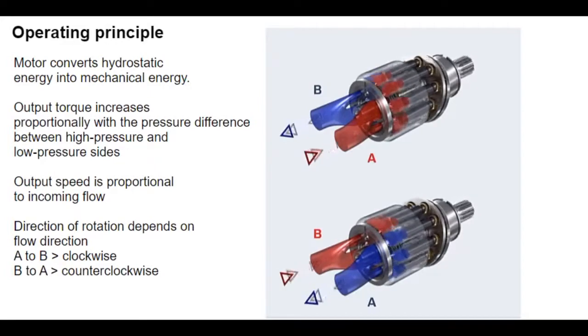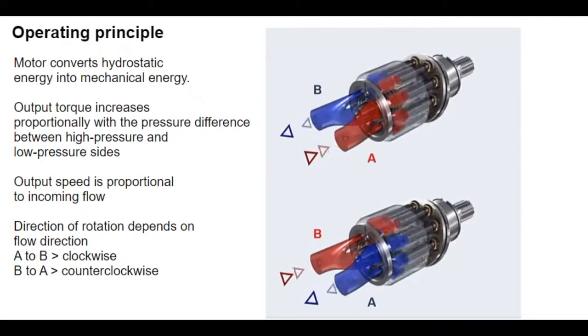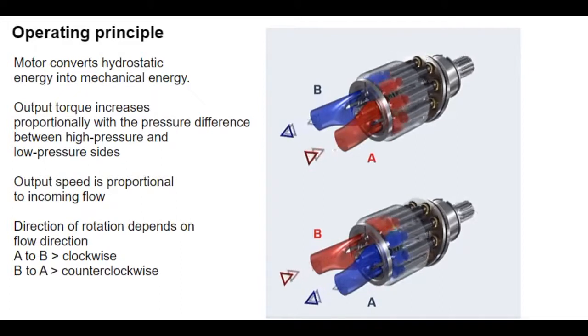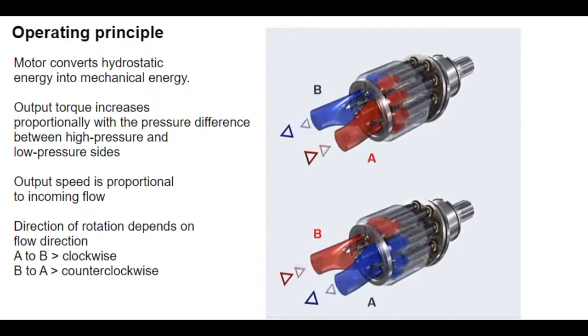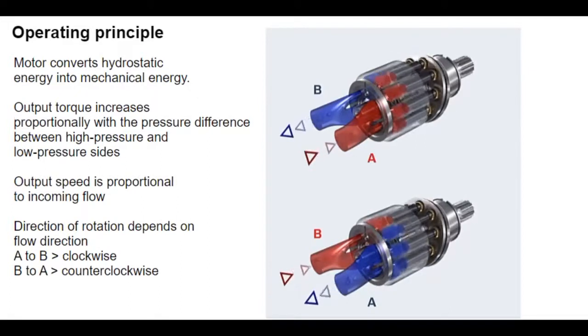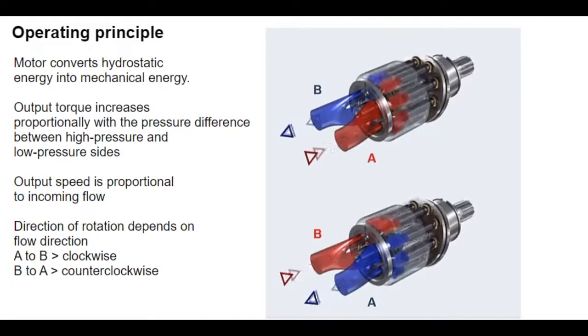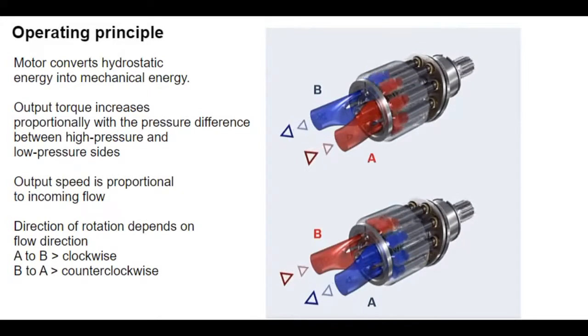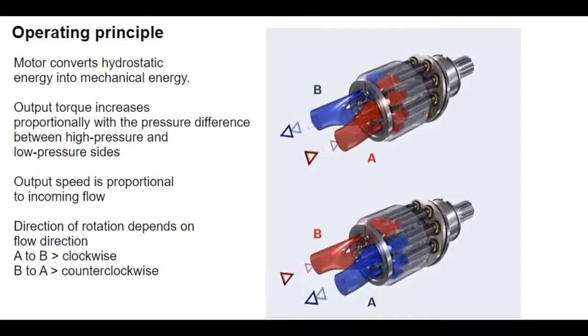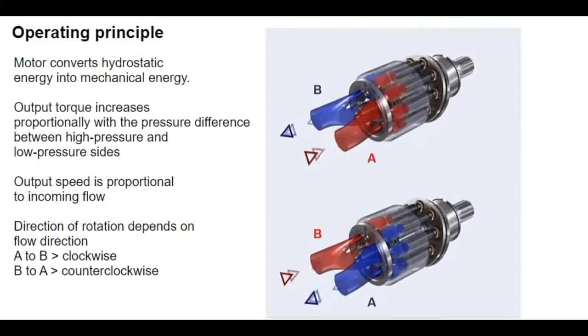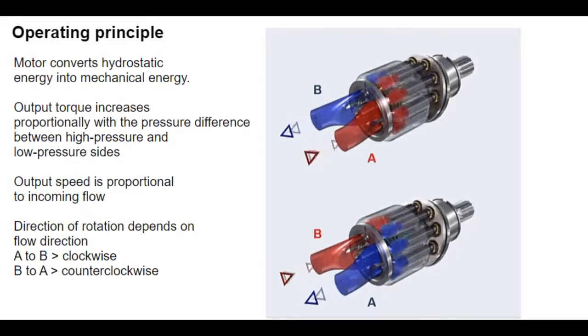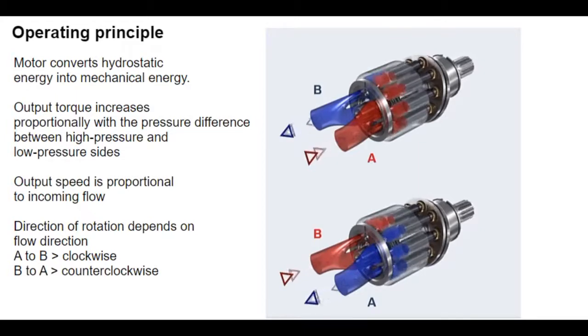Output torque increases proportionally with the pressure difference between the high-pressure and low-pressure sides. The output speed is proportional to the inward flow and inversely proportional to the displacement of the hydraulic motor. If hydraulic fluid is supplied from the A side (left), the motor rotates clockwise. If it is supplied from the B side (right), the motor rotates counterclockwise.